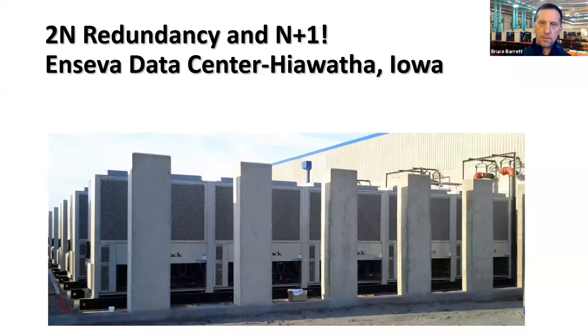Interestingly, inside the building, three Grundfos pumps, they had an N plus one configuration on the pumps. The two banks here had two different power supplies from two different electrical companies. So the highest level, the highest tier data center, full 2N redundancy.